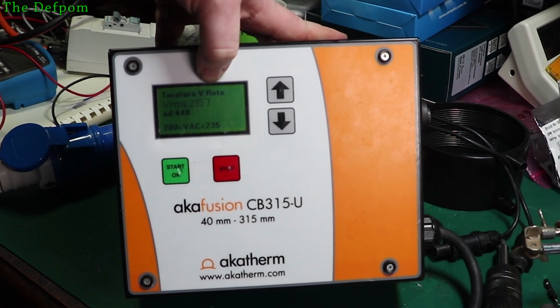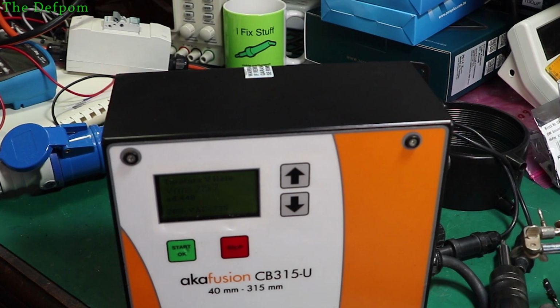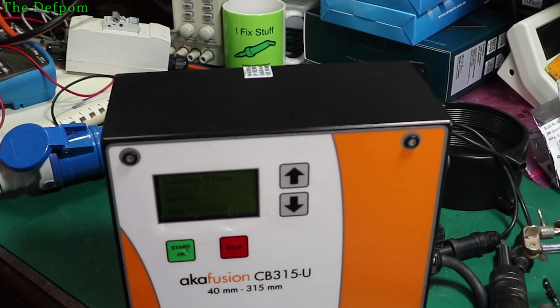Found some other resets. There's a full reset as well. Completely resets it, then you have to do some other stuff. Reset to default, which is 1333, is the one that does reset default. There's also 1400, which says wait for writing to USB memory. And there's 1970, which says press OK to start calibration. And I haven't pressed OK. I've left that alone. I'm not sure what the calibration criteria is supposed to be, so I don't want to risk messing up the one that's already in here. I think that doing 2100 reset the maintenance alarm after I'd done 0122 and then 1333 and then 1100.